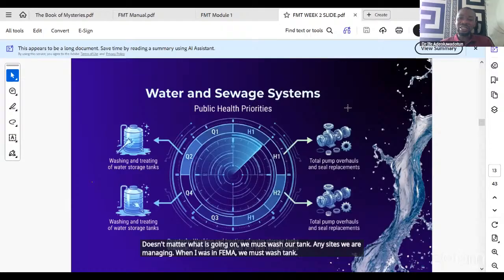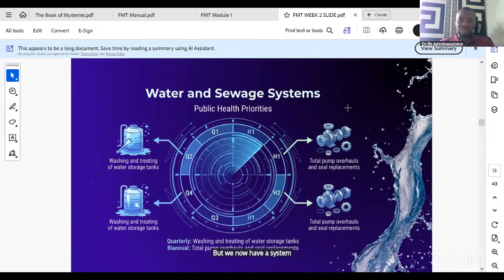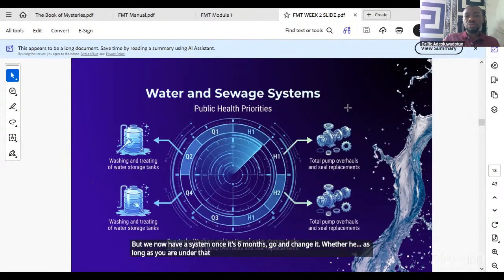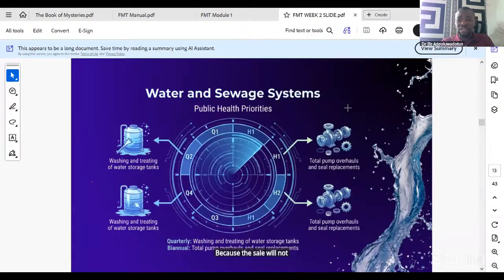One thing very scarce, that people don't do, is run to failure maintenance on the seal. We now have a system to say once it's 6 months, go and change it, whether or not you are on that pump every day. Because the seal will not alert you that it's going to fail today. So it won't let you know.